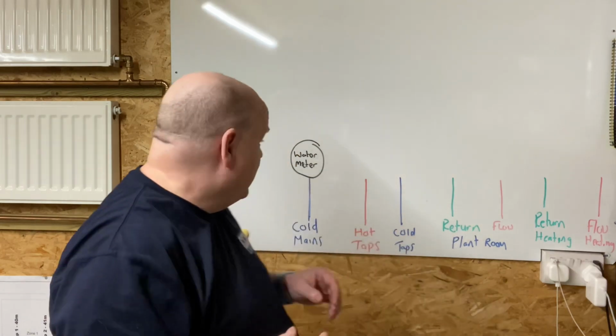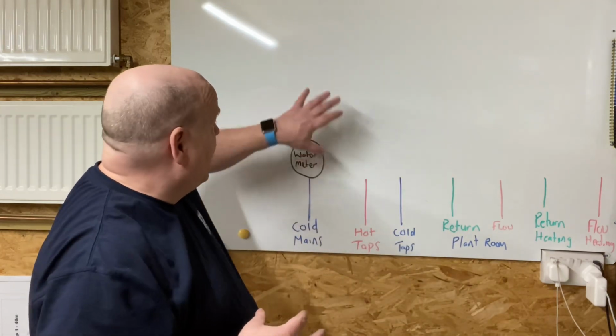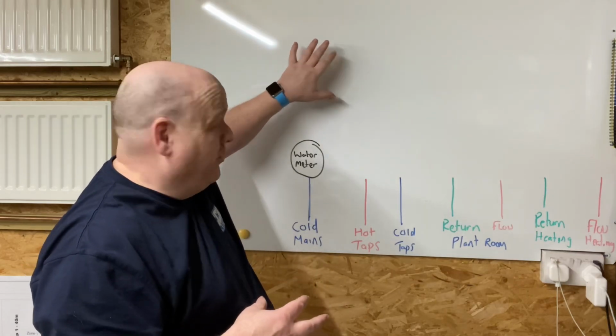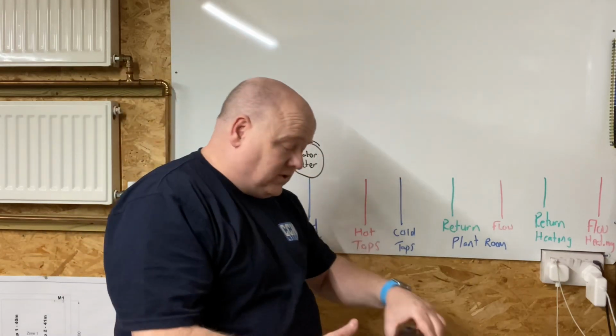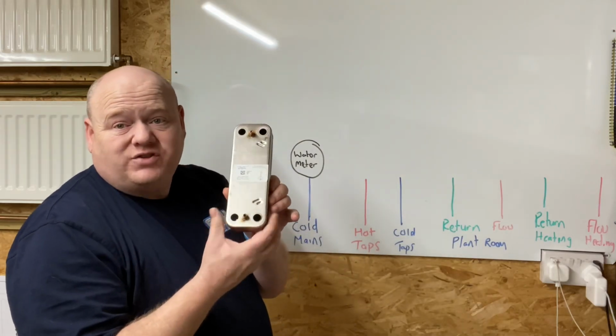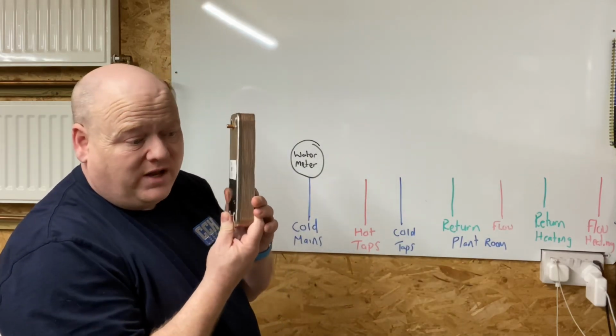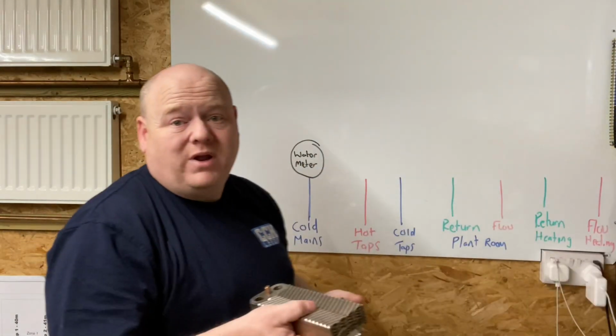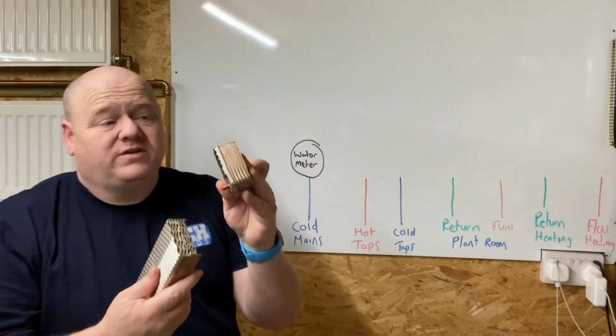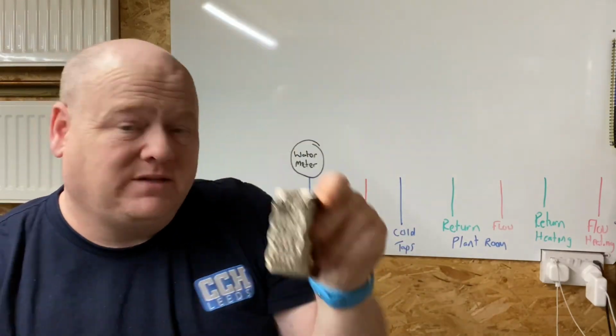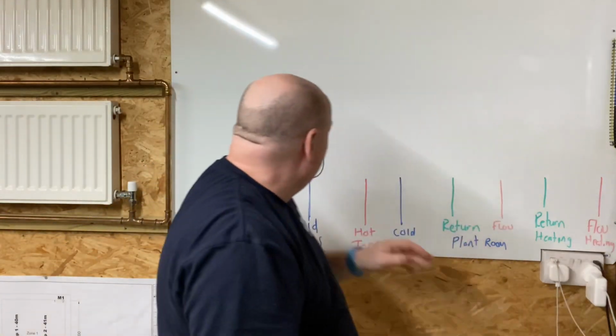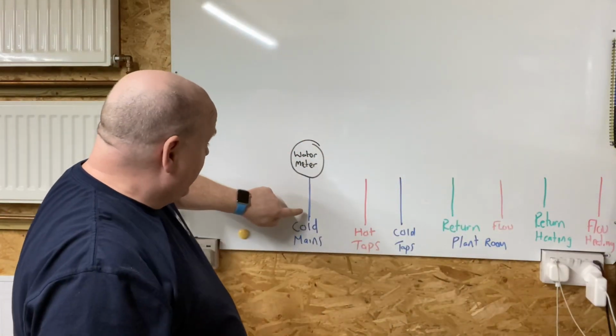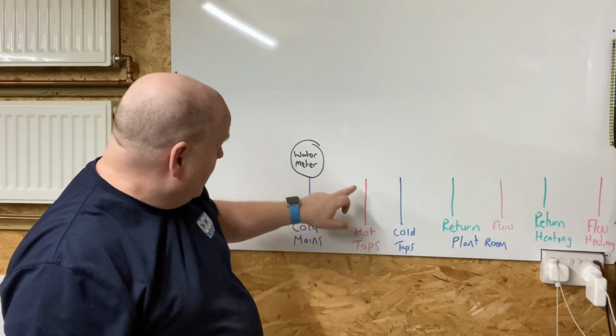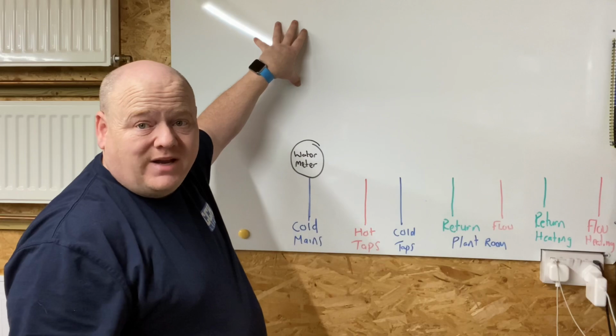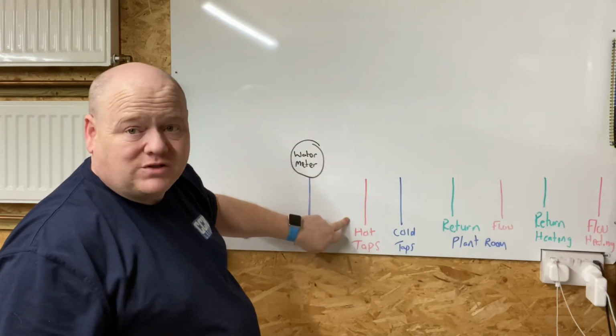So now what I'm going to try and do is explain how these build up to the different components on here. So first of all, we've got plate heat exchangers in this one. So we've got 2 plate heat exchangers. And what do plate heat exchangers do? They transfer the heat via the plates. So what we're trying to do in this particular case is, when this cold water comes in, it goes through the plate heat exchanger, it gets warm, and then it goes out to the hot taps.